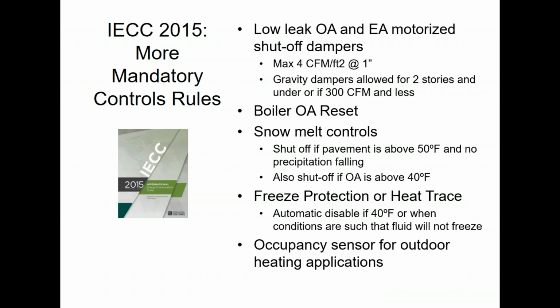concerned with. If you're going to do heating outdoors, for one, the heating must be radiant. That's the only type of outdoor heating allowed. It means radiant tubing in the concrete or an infrared heater overhead. Those would be allowed types of systems. Additionally, those systems have to be on an occupancy sensor, like a motion type sensor. You can't just have those turned on a switch because people put them on a switch, they turn them on, they forget them being on, and they forget to turn them off for several days. They got to be on an occupancy sensor, so you need that type of control with you.